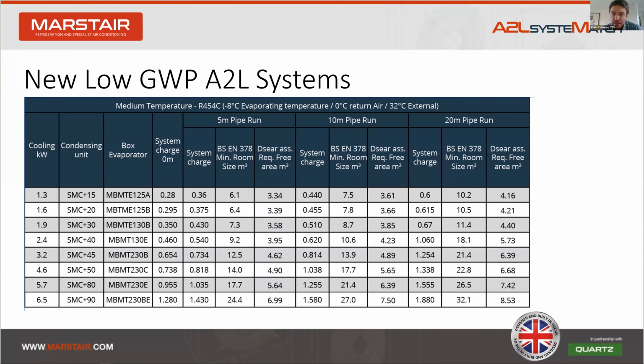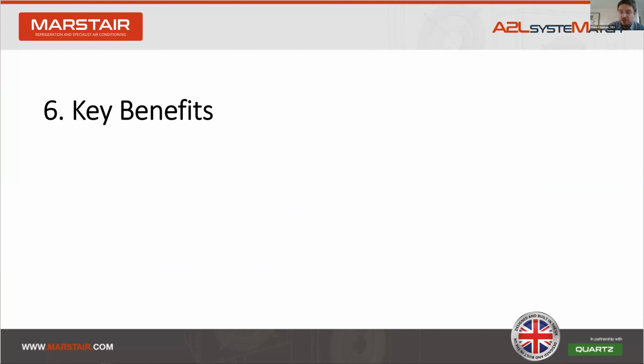We also provide guidance for the free volume within the cold room, so it can be discussed with the end user at the specifying stage. All the work we've completed on our critically charged systems allows us to offer systems with refrigerant charge levels low enough to meet the stringent requirements within the standards on a reasonable length of pipe run. Okay, so we're just going to do a quick run through the key benefits.